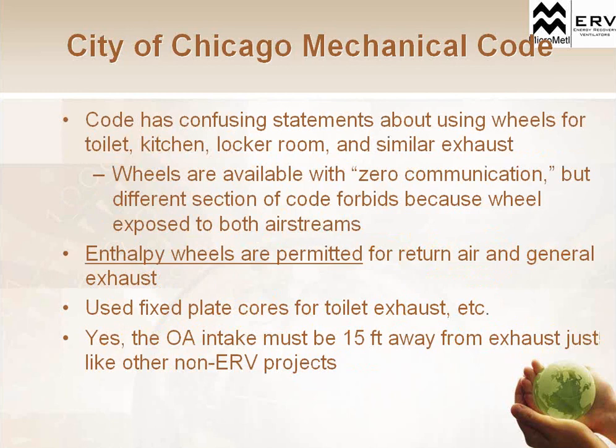Fixed plate cores, just as a sidebar, are usually used for a smaller CFM size. Each fixed plate core usually is designed for about 500 CFMs. You can bank multiples of those fixed plate cores to go up to 2,000, 2,500 CFMs, but then it becomes cost prohibitive. Unless you're in the City of Chicago where they require you to use those fixed plate cores anytime we're using toilet exhaust as part of your exhaust from your building.